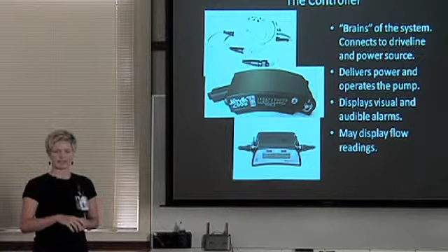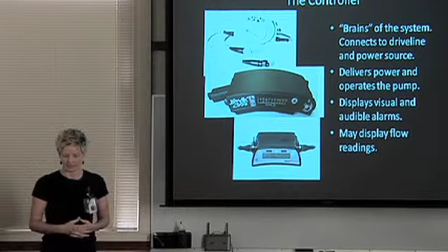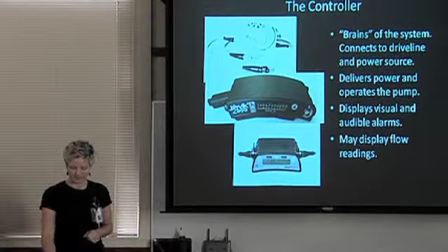As we said, there's a drive line that exits the body that has to be connected to power. There's no such thing as a fully implantable device yet. So the brains of the system is the controller. It delivers power and operates the pump. It displays visual and audible alarms, and some, like the HeartMate or HeartWare at the bottom there, may display flow readings as well, so everybody can see what their flows are.